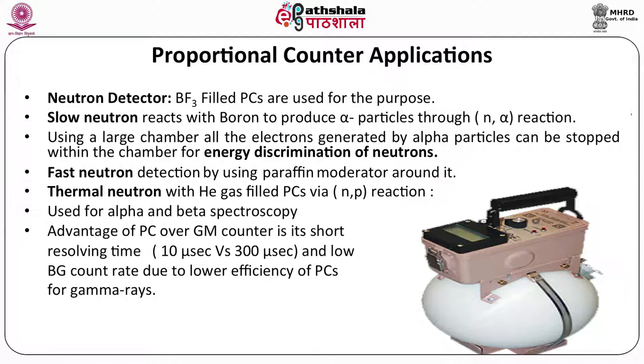Proportional counters are mainly used for neutron detection. Boron-filled proportional counters are used for this purpose because slow neutrons react with boron to produce alpha particles through an (n,α) reaction. Alpha particles are charged particles and are intensely ionizing, so neutrons are detected indirectly. Those alpha particles produce further ionization in the BF₃-filled proportional counters and the resulting current is measured. Using a large spherical chamber filled with BF₃, all the electrons generated by alpha particles can be stopped within the chamber and we can determine the energy of the neutron source.